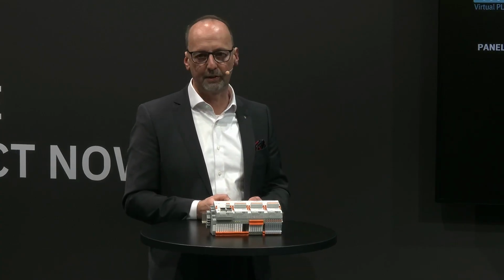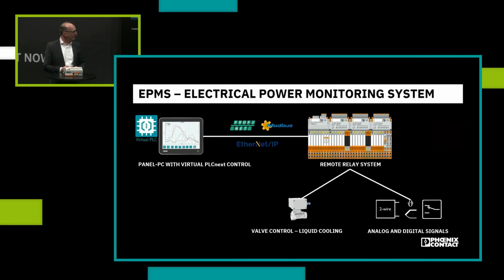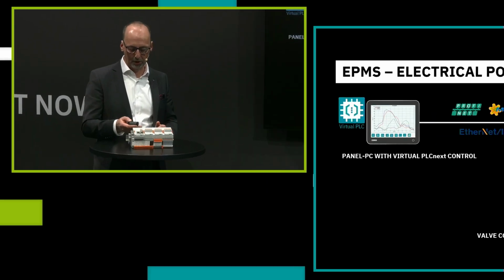In this case, it's Modbus TCP. The remote relay system itself is able, due to different pluggable modules, to be connected to analog signals. For example, if I want to monitor temperature, as you can see here, via two-wire connections, that's possible at the input side. On the output side, we can use the outputs to control valves when it comes to having optimum flow into cooling systems and making sure that the highest uptime is possible within the data center itself. Of course, that could also be other control systems, or other networks that would speak as well. But this is actually a real-world use case that we've been working on with our customers in the United States.